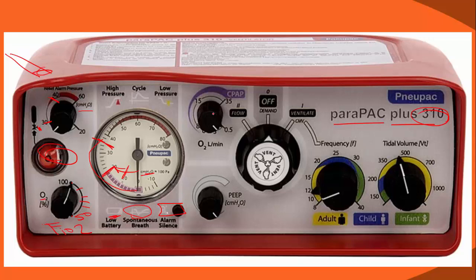All right. So looking at the CPAP setting, you can change this only to flow so that there's no ventilation, and that would give us CPAP. And CPAP here is giving us our range of settings, essentially for PEEP, so our flow setting. So generally CPAP hangs out at about 10 centimeters of water. You can set PEEP here independently so that we can use it on the ventilator, in kind of the same range, and the PEEP will be represented somewhere on this device.